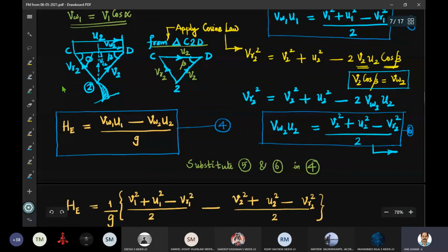Similarly, from the outlet velocity triangle, which I have drawn separately, the vane tip at outlet is shown here. The velocity triangle at outlet is this one, as we explained before. The relative velocity component is VR2, U2 is the velocity of the blade at outlet, and V2 is the absolute velocity of the fluid at outlet. If you consider these three, VR2, V2 and U2, and the angle between V2 and U2, that is beta, the guide vane angle at outlet.